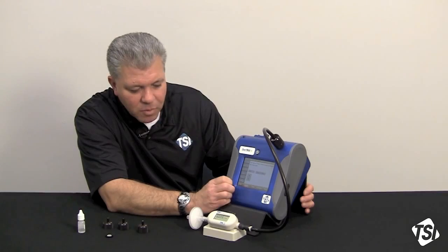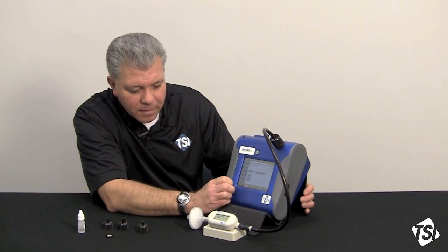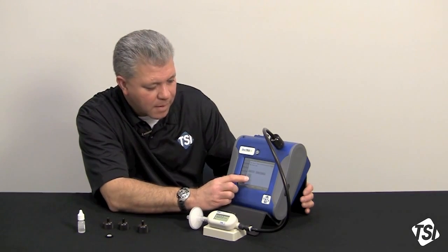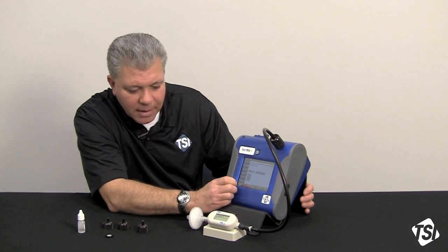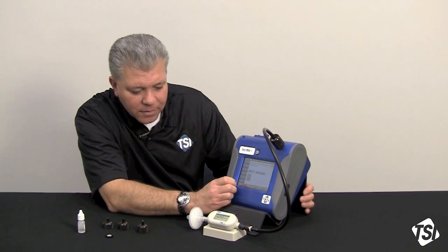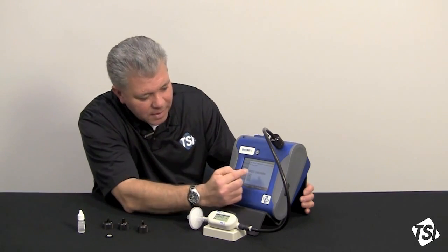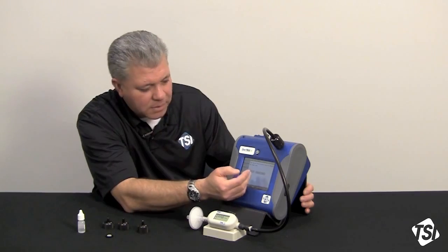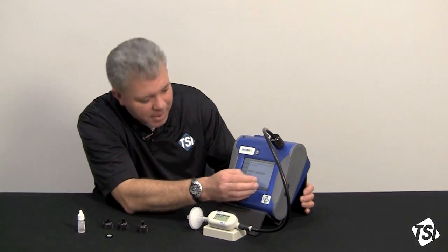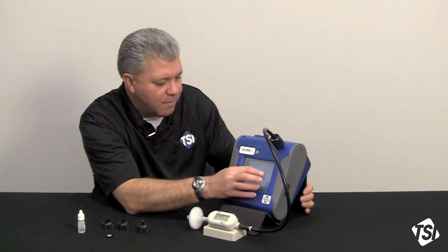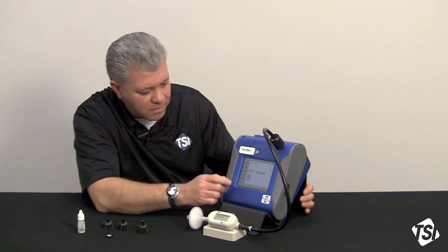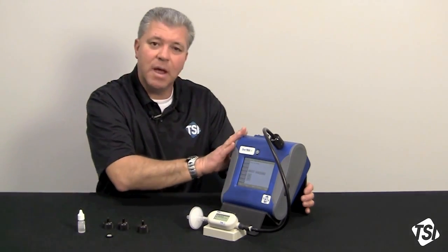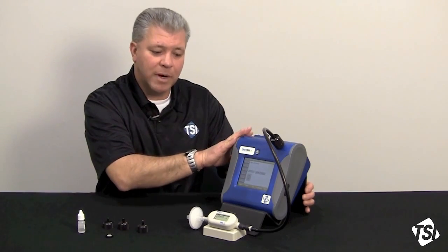And I'm going to touch it one more time, and we're getting it down to, all right, I've got 2.998, 3 liters, we're set. Over here towards the right, you have an undo and a save button. I am going to hit the save. I want to save that calibration value, and now we're essentially done doing a flow calibration.